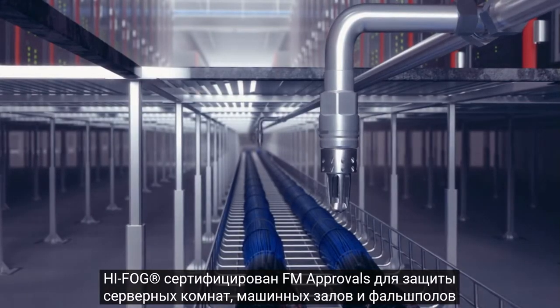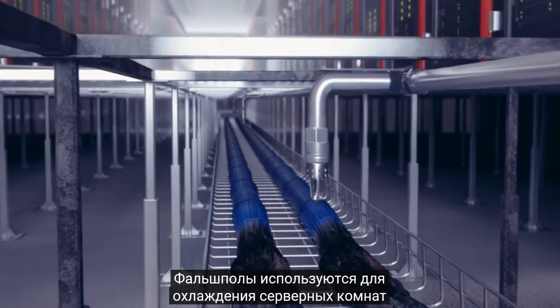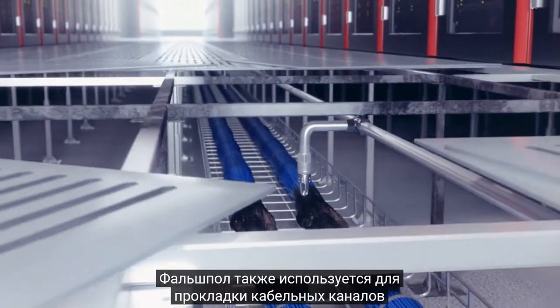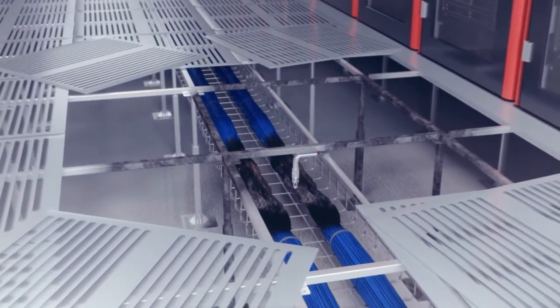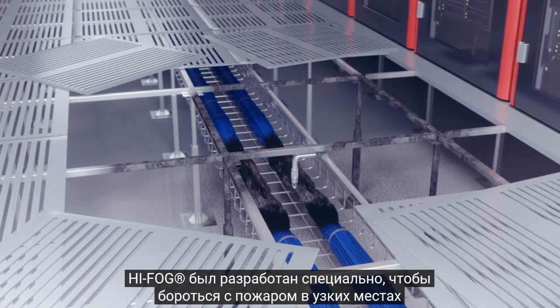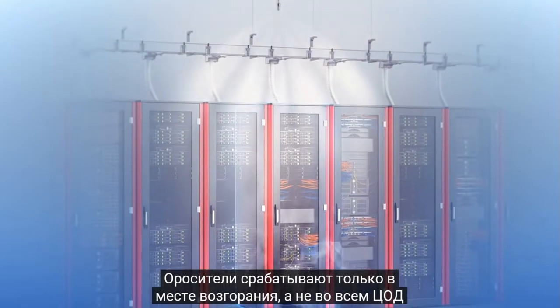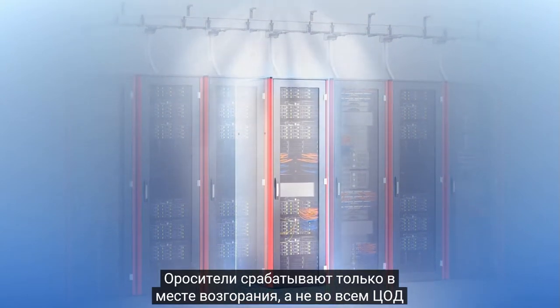HI-FOG is approved by FM Approvals to protect the server rooms, also known as white space, and subfloors. Subfloors are used for delivering process cooling to servers and are also often used for laying cable racks. Cable fires can be really difficult to extinguish. Appropriately, HI-FOG has been designed to fight fire also in the narrow spaces under the data hall. Water is discharged only to the area of fire, not to the entire data hall, subsequently preventing flooding at the premises.